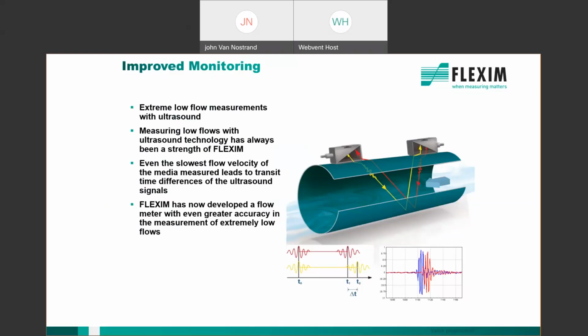FLEXIM's strength is not only being non-intrusive, but also measuring very low velocities or fast-moving media. Our ultrasonic technology is able to do extremely low velocities or extremely fast-moving velocities. Even with low velocities, we can detect down to 0.03 feet per second, and with a specially calibrated meter, 0.003 feet per second.